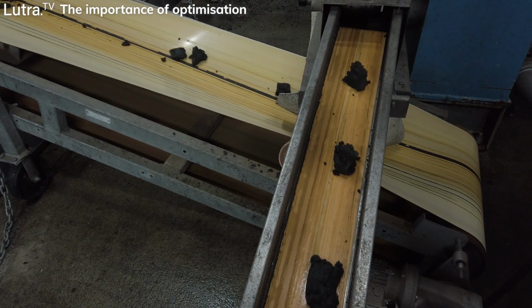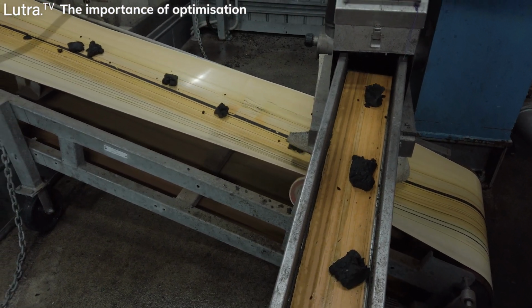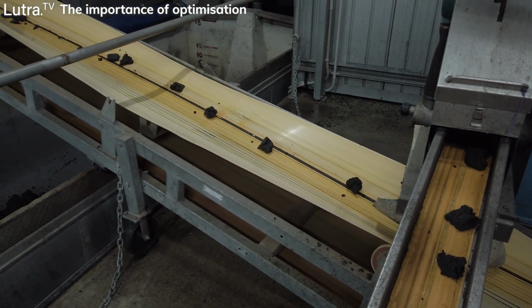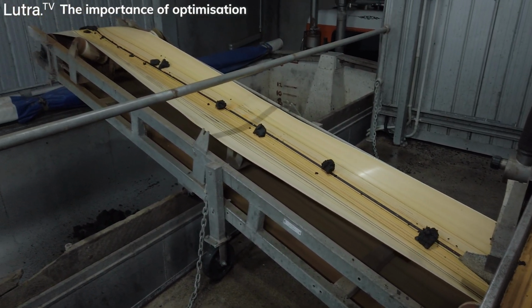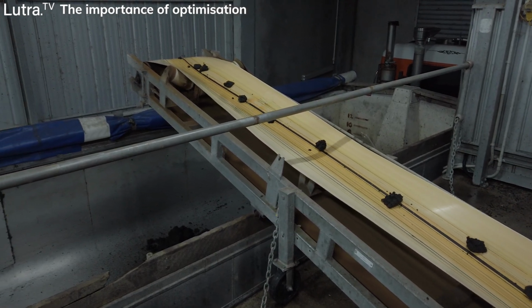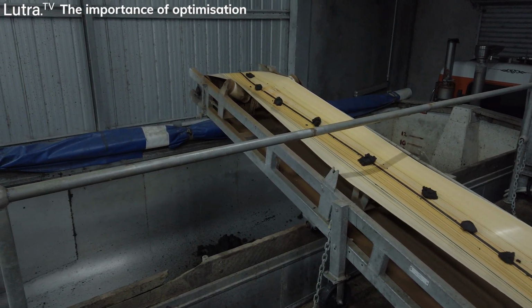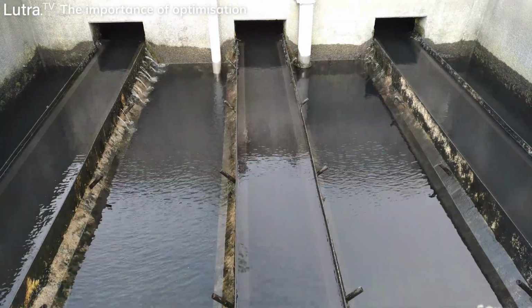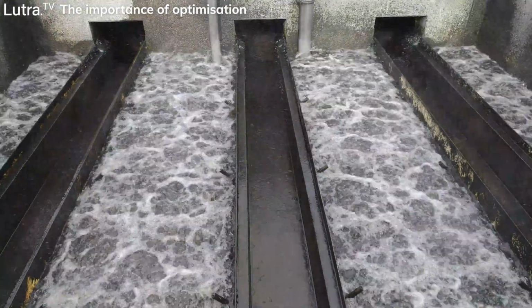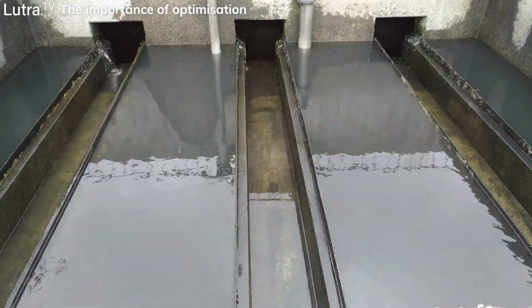And another area might be the waste, be it water or solids, that a plant is generating. Plants have certain levels of efficiency. Water comes in, waste goes out, solids are produced. Things like reducing the coagulant can thereby also reduce the solids that are produced. And by improving things that are not necessarily relating to the dose rate, like the strength of the floc and the performance of filters or clarifiers, you may not need to backwash as much on your filters, therefore you generate less water waste, therefore you produce more treated water and you make the plant more efficient.